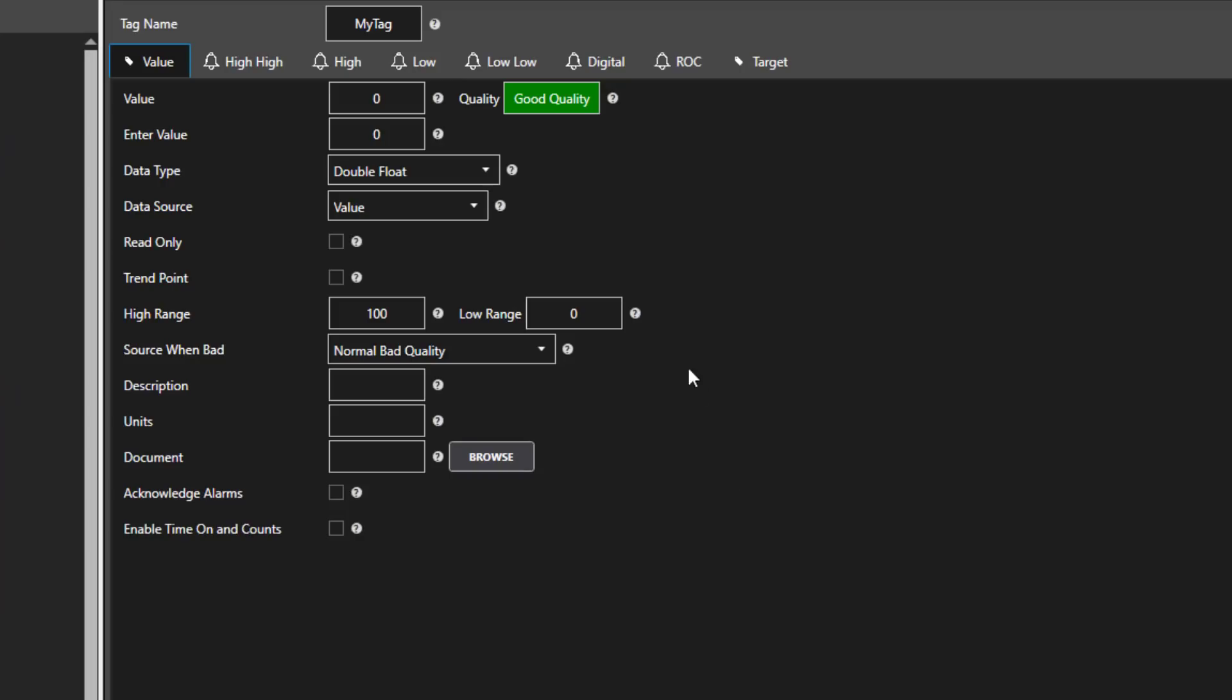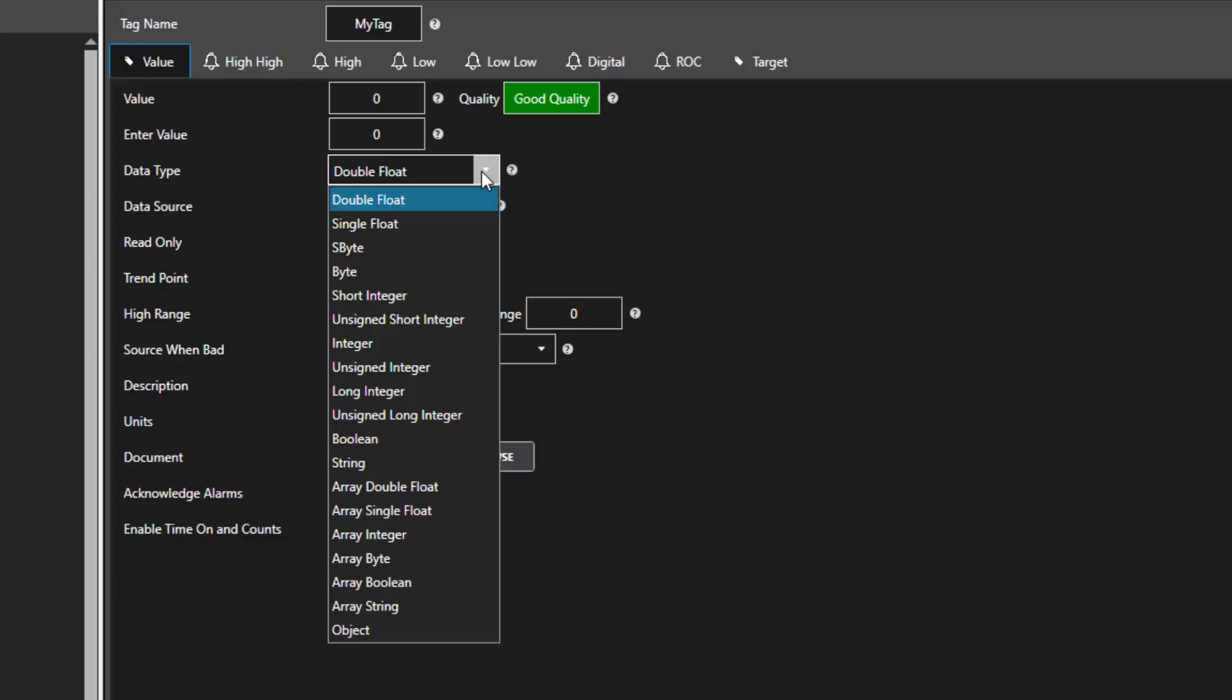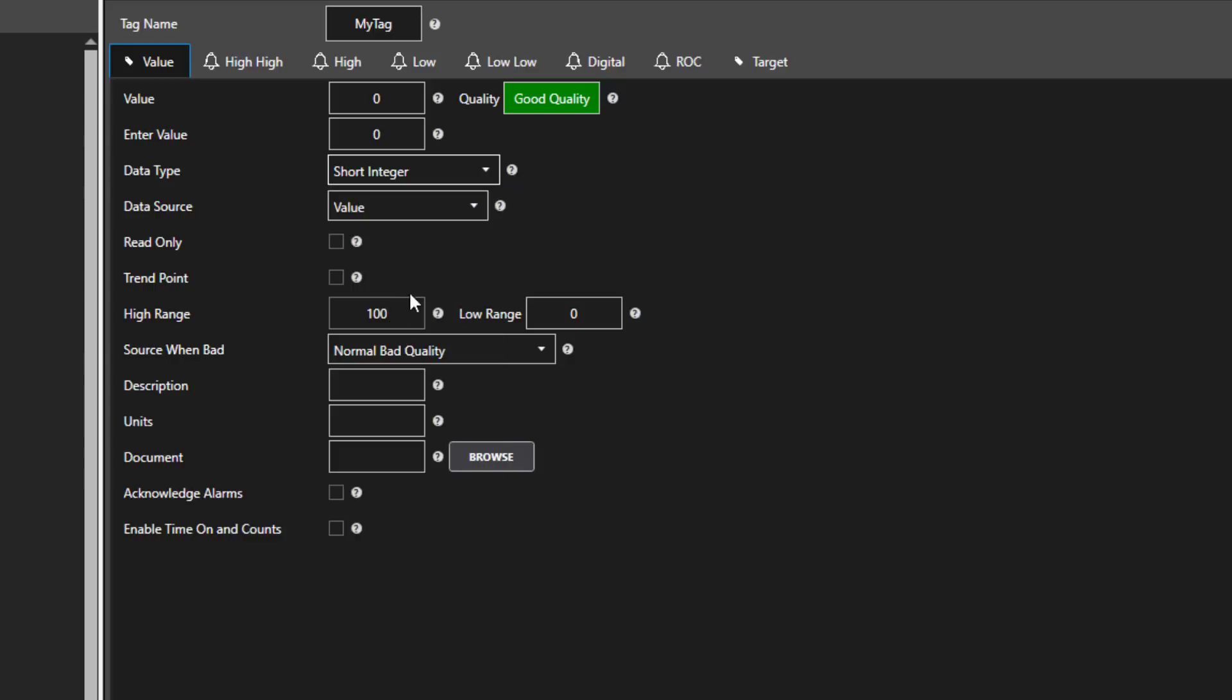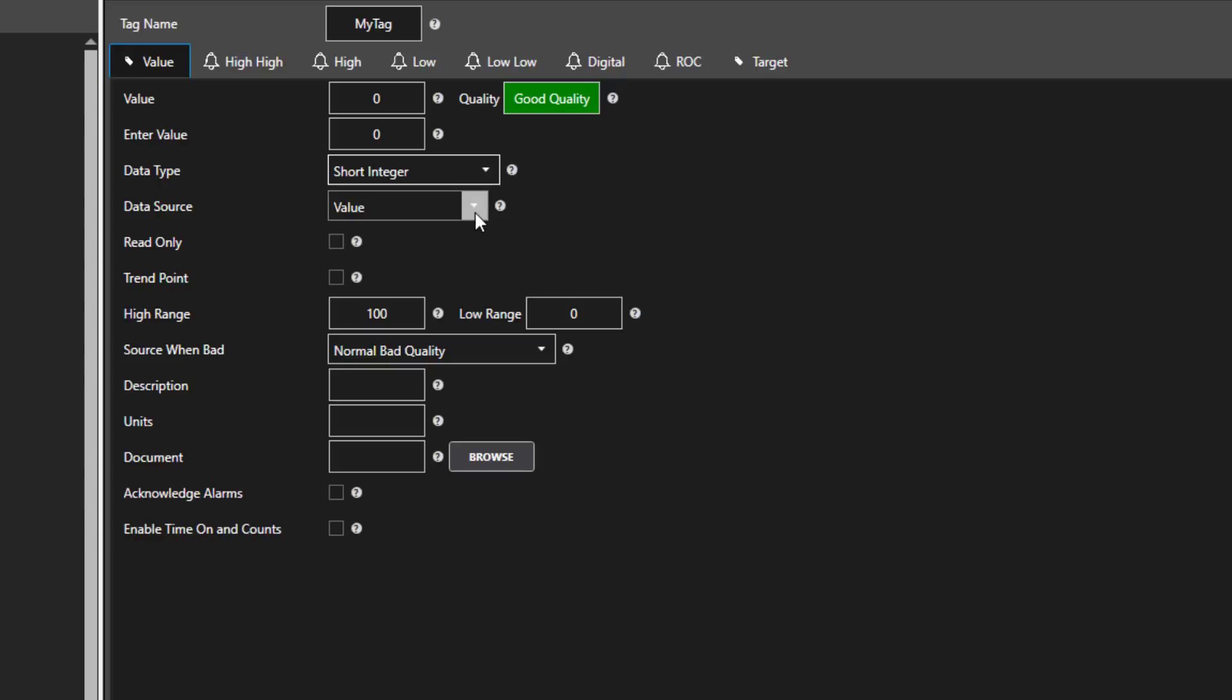Here we can specify the data type of the tag value. This is going to convert the value we receive from Modbus to a known type. If you don't know what it is, you could use Object. That would handle anything. In this example, I am going to use a short integer, which would be a 16-bit integer.